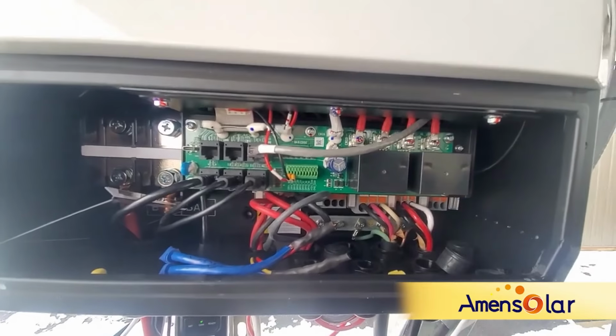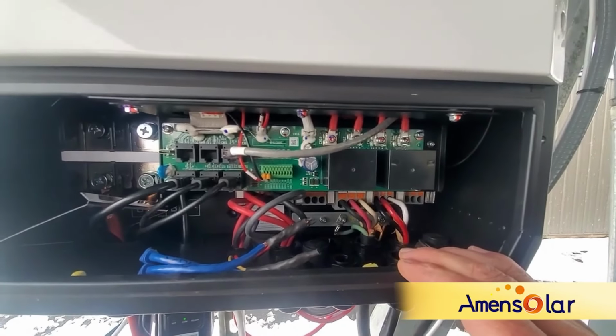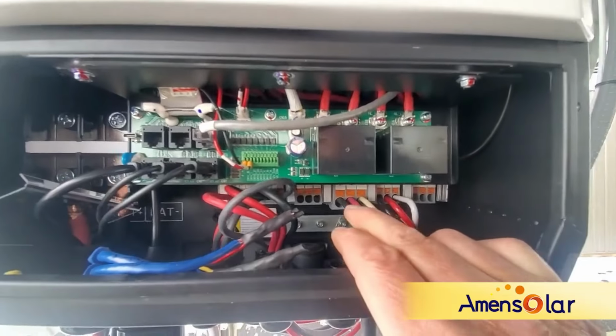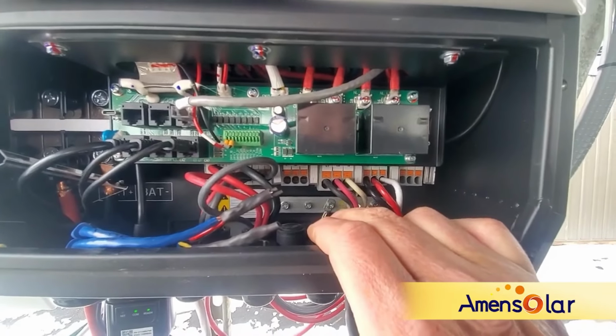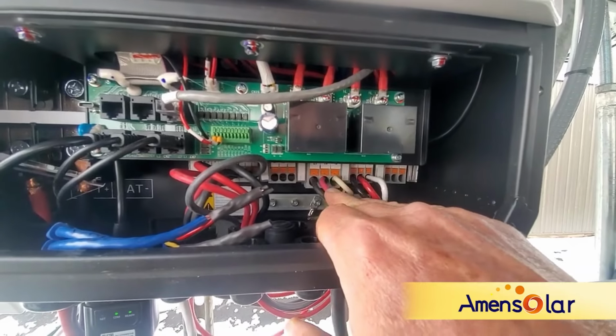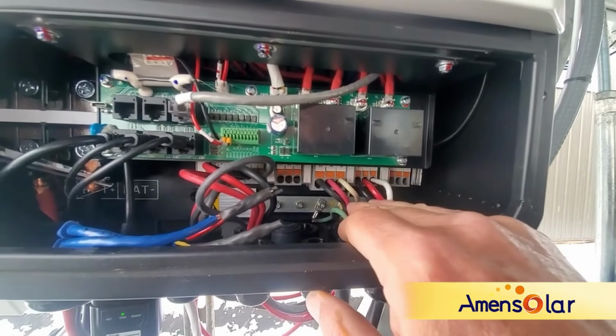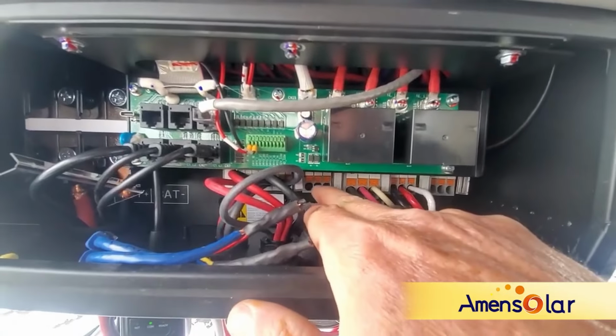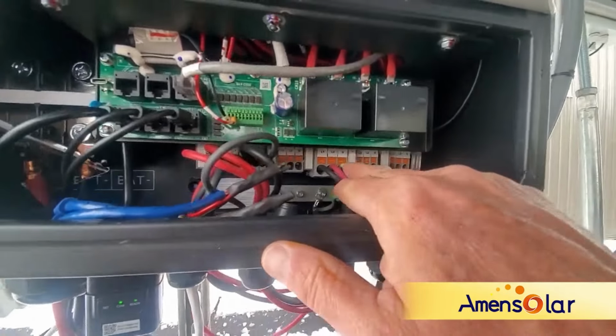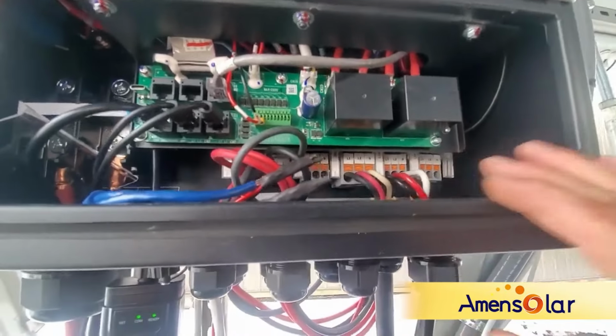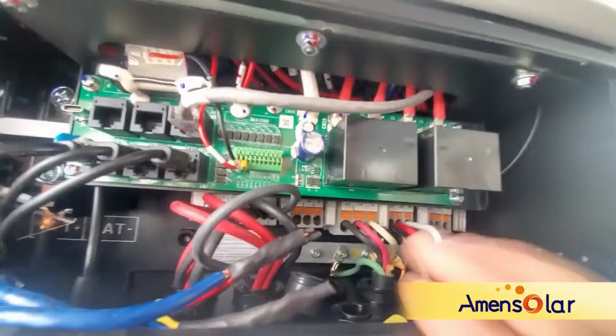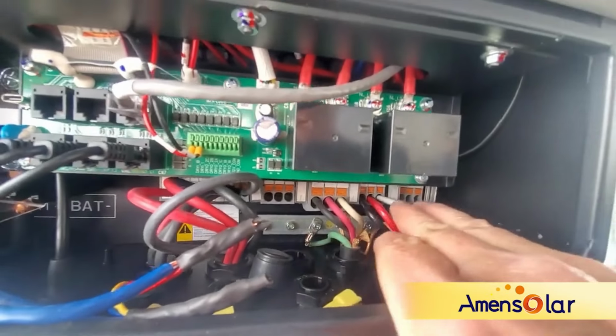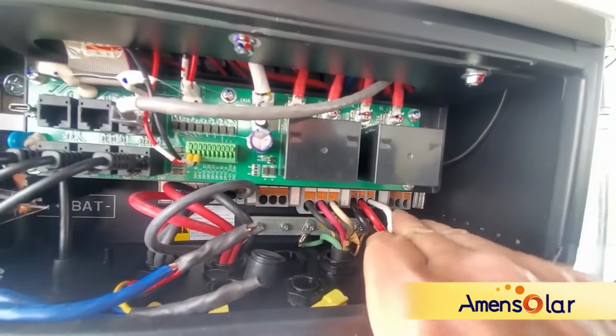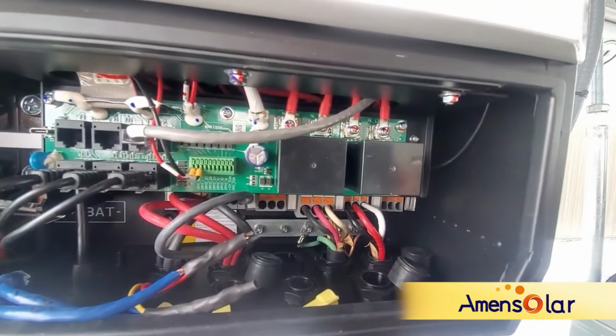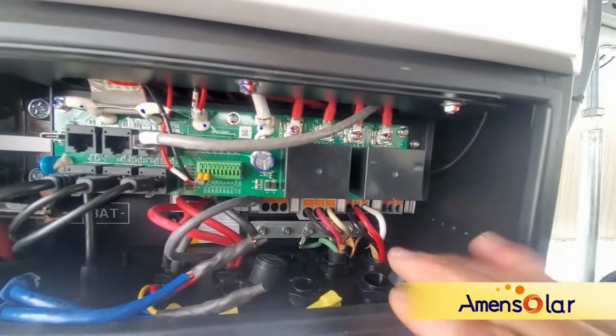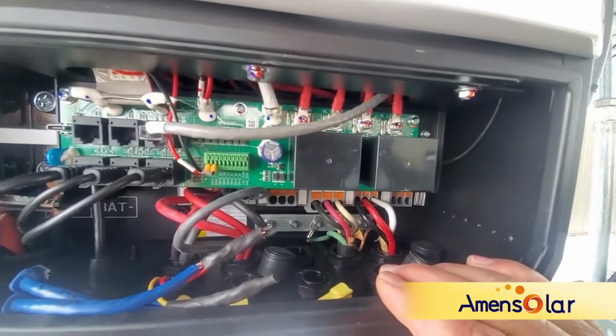Now, also pretty unique, most of the Sol-Arks and the Lux Powers and that have got a generator input which can be used as an input or an output, and then it's got a load 1 and a load 2 output. Now this particular unit has got a generator input, a grid input, a load 1 output and a load 2 output. And you can program the load 1 and load 2 outputs. You're just going to switch a relay over here based on the state of charge of the battery.